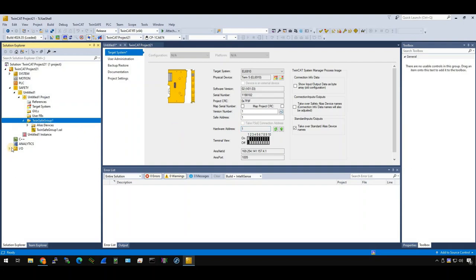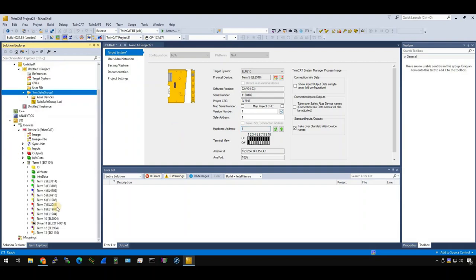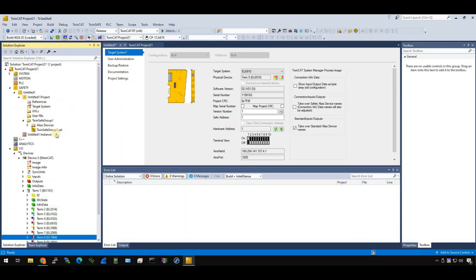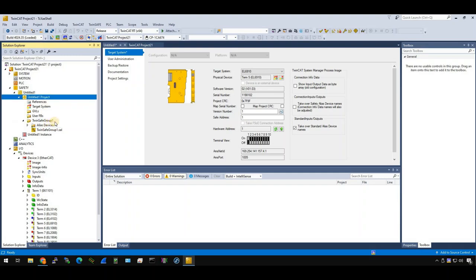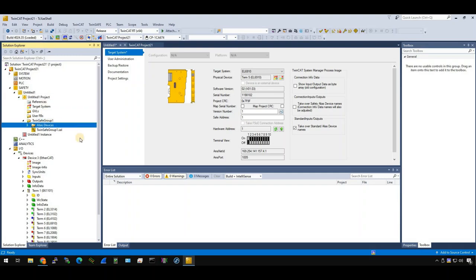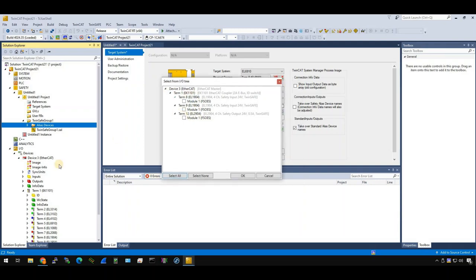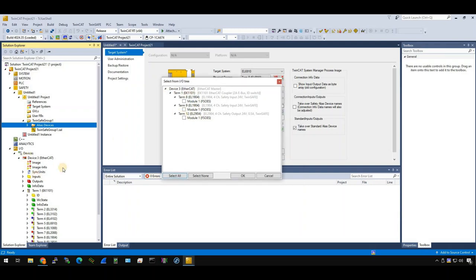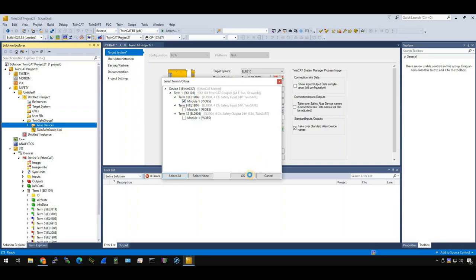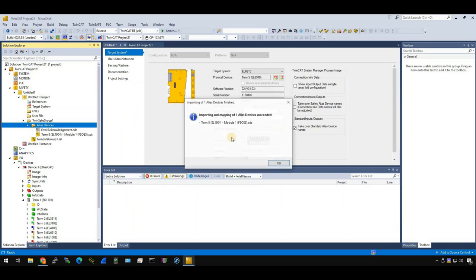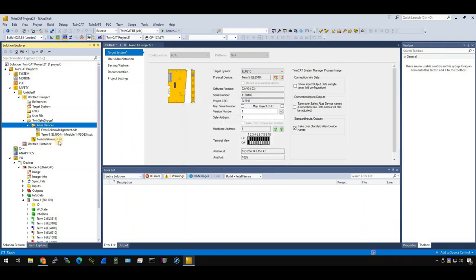We can import this safety logic terminal into our safety project. How can we do it? Just open your safety project, go to safety group 1, alias device, right click, import alias device from IO configuration. When I click it, you can choose the device that you scanned before. Okay, in my case, the EL1904 is used. So click it. You see in the signal, the terminal is imported without any error. Good.